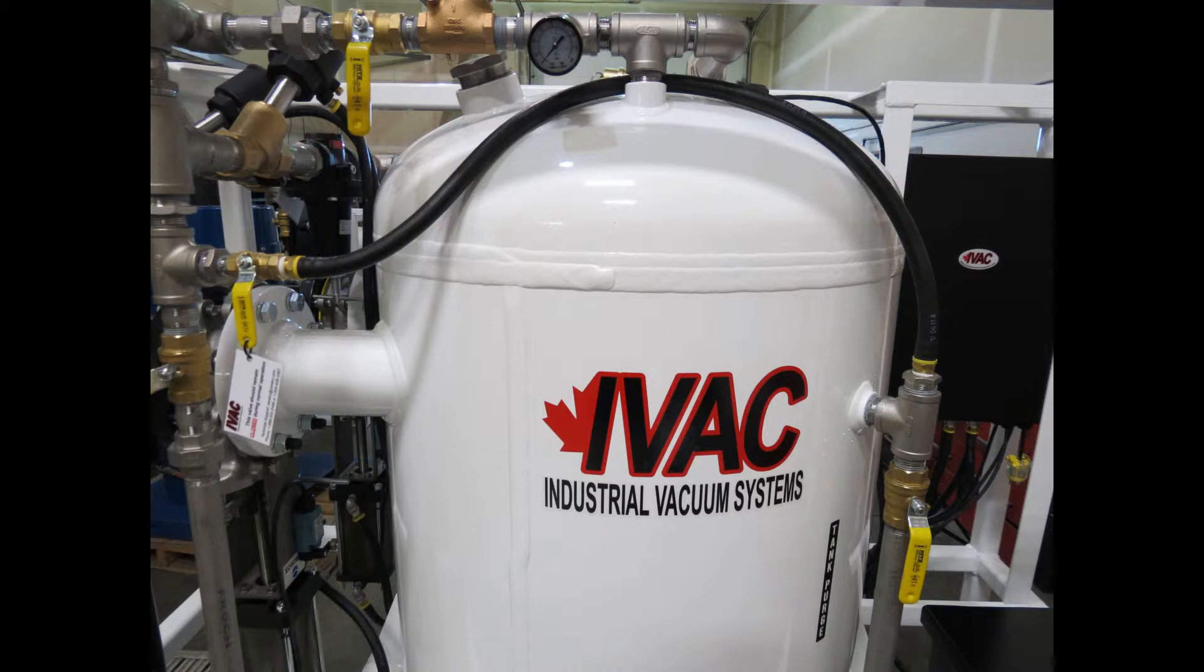The pilot pressure in turn opens the discharge air angle seat valve, allowing air to flow into the vessel by going through the discharge air regulator and the two 1-inch ball valves that control the discharge air pressure and volume.